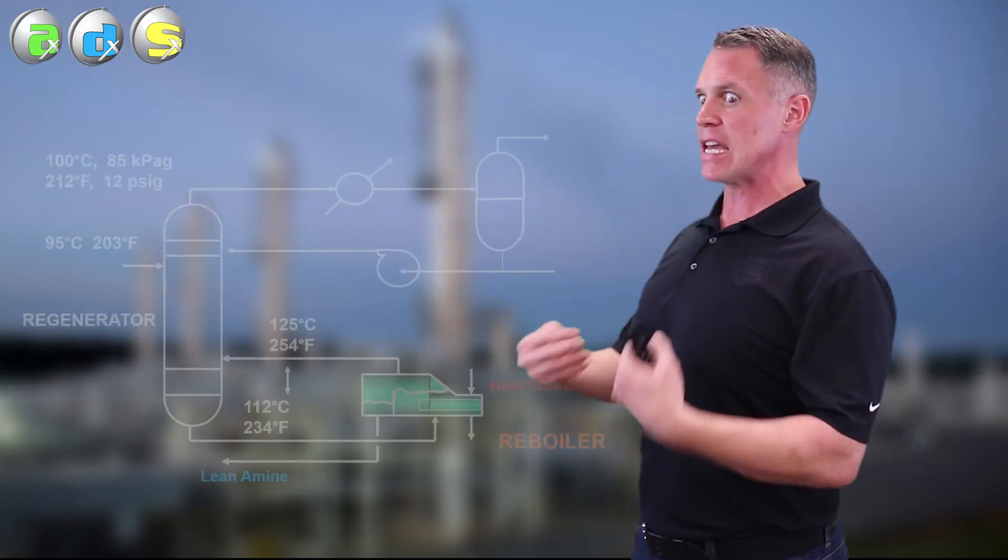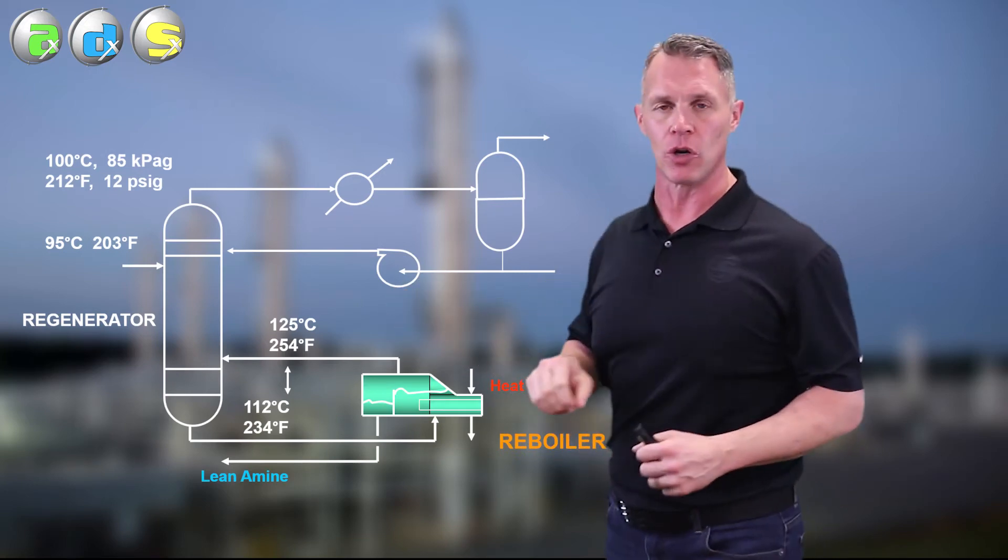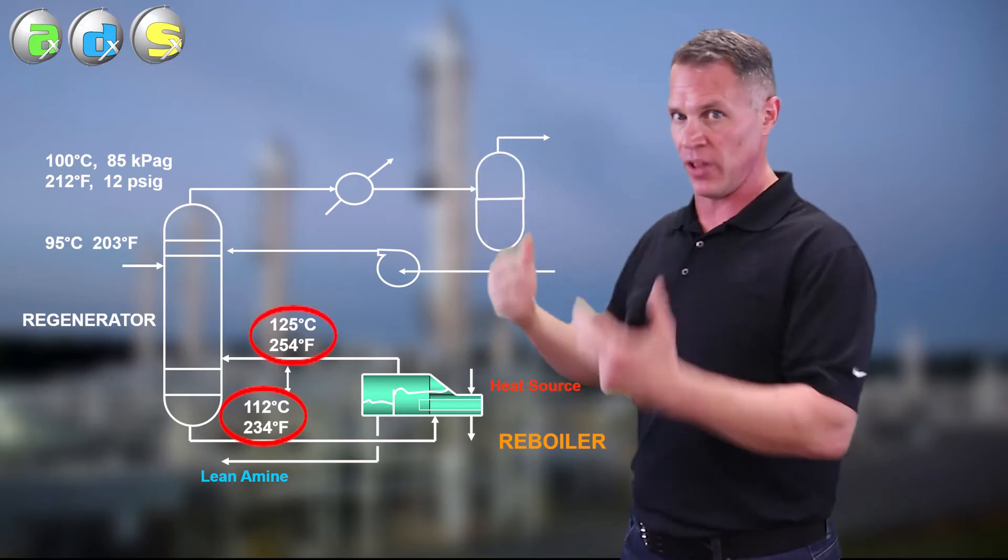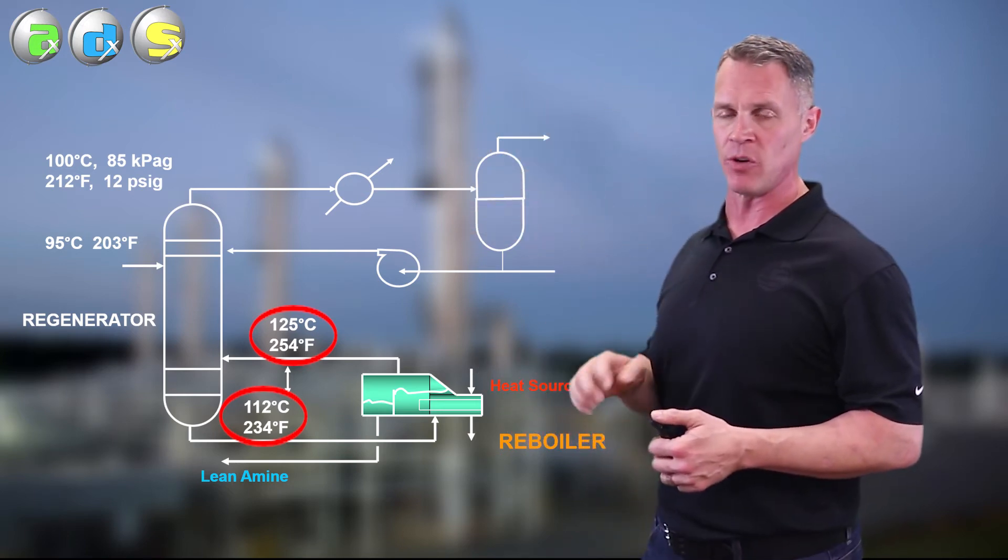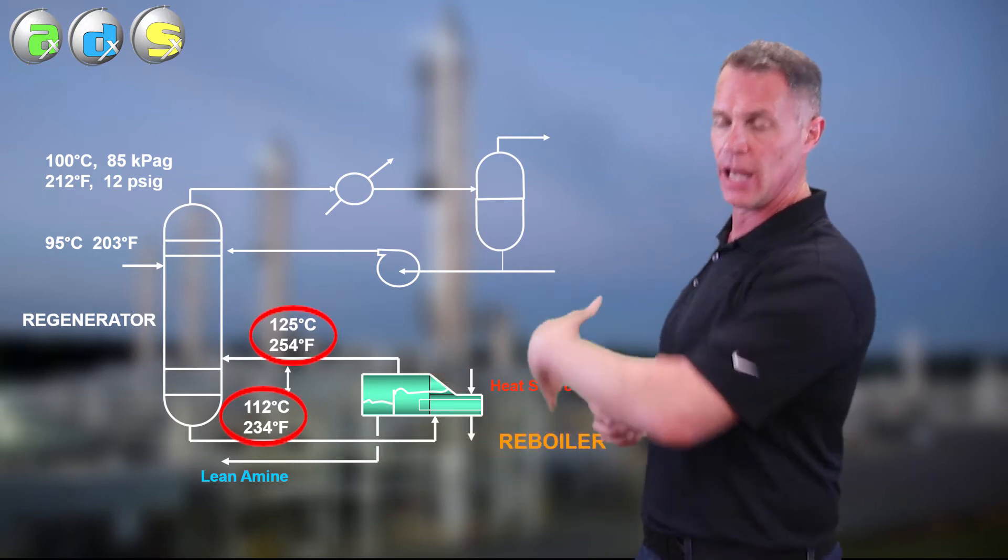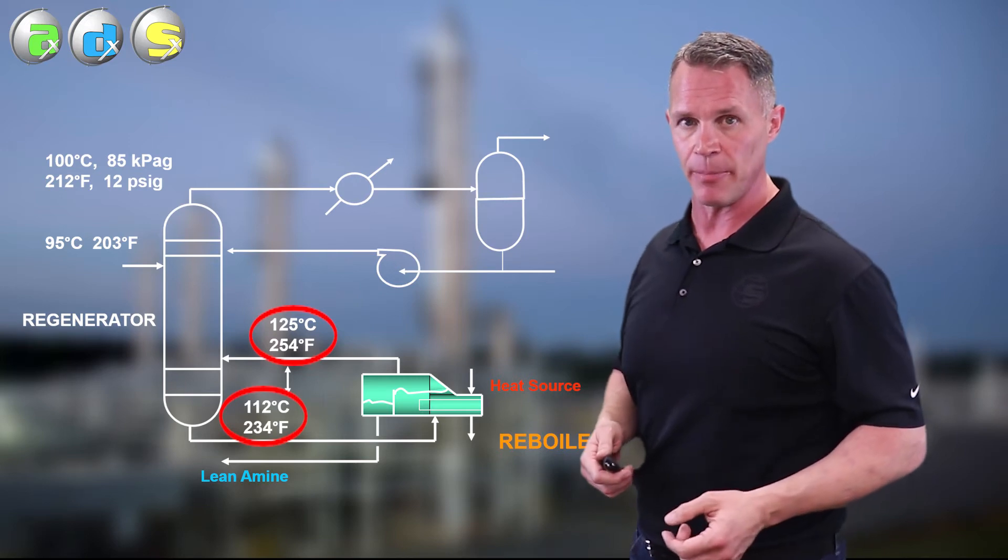Now, how could the operators have known this was happening? Most regenerators do not have temperature indicators throughout. So they don't know what the temperature profile is. And they therefore don't know what's happening to the CO2 in there. Well, if you're lucky, your DCS screen will have temperature of the liquid feeding the reboiler as well as coming out of the reboiler. Or the reboiler temperature itself, either one. What you do not want is there to be a difference in temperature, more than a couple of degrees difference in temperature. Basically, you don't want cold amine into a reboiler and then hot amine coming out. Because that tells you that the reboiler is having to heat up the amine.